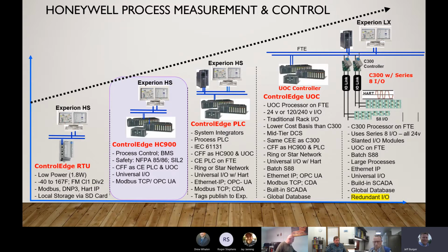The next slide shows a little bit about the HC900 CONTROLEDGE family. If you move from left to right, the base functional unit would be the CONTROLEDGE RTU, again used in remote applications, remote I/O. It has a very low power consumption of 1.8 watts, so it can be used in applications where you might have solar panels or battery operated systems powering the RTU, applications where you might not have access to local power. It also has a lot of different communication options. It has Modbus, DNP3, HART protocol, and also Ethernet IP. This allows the RTU to communicate to field transmitters that utilize these protocols, or it can talk to third-party devices and gather information and use it in the control scheme.